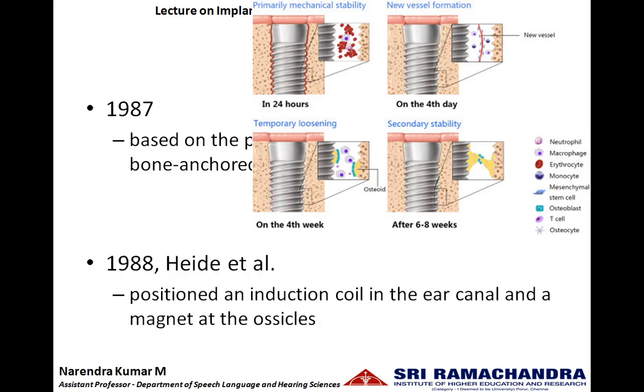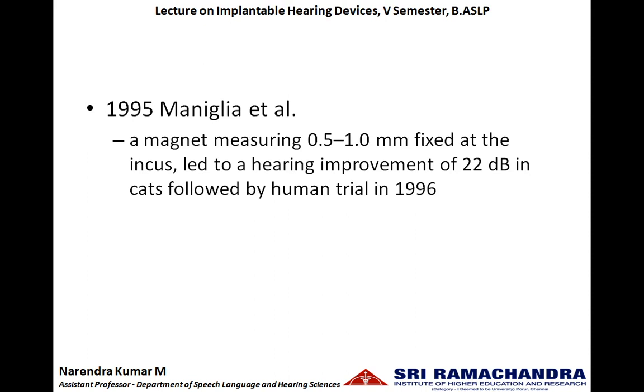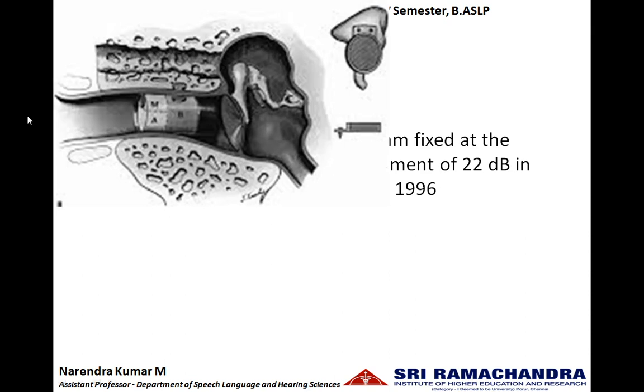In 1988, Heide et al. advanced the electromagnetic middle ear implant by positioning an induction coil in the ear canal and a magnet at any part of the ossicle. In 1995, Maniglia et al. placed magnets of 0.5 to 1 mm at the incus. This position led to a hearing improvement of 22 dB in cats, and they did human trials in the year 1996. The sound from the external environment was picked up by the microphone placed in the ear canal, amplified, and sent to the induction coil. This induction coil created magnetic fields which were picked up by the magnet implanted at the incus, causing the magnet to vibrate, the incus to vibrate, and the vibration to be sent into the inner ear.